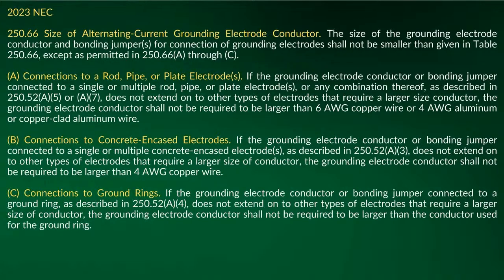Yep. Okay? And when you look at (A) and you get the rod and pipe and plate electrode, you need a number 6 copper. Then you go to concrete encased electrode, it's a number 4 copper. Yep. And then to a ground ring, it's a number 2, which you'll pick up in 250.52(A)(4). Okay, so yep. I'm just putting that out there now, and I'm going to prove this point in a minute.